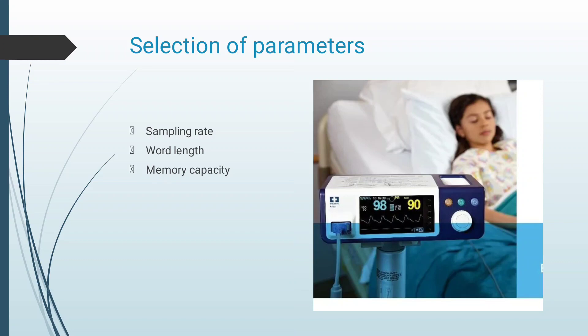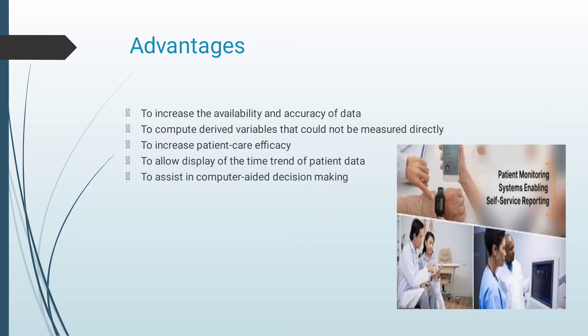Memory capacity: it contains the memory for each signal and displays each channel. Stored signals must be scrolled on a CRT display with a time interval. Advantages of the patient monitoring system: it increases availability and accuracy of data, computes derived variables that could not be measured directly, increases patient care efficacy, allows display of the time trend of patient data, and assists in computer-aided decision making.